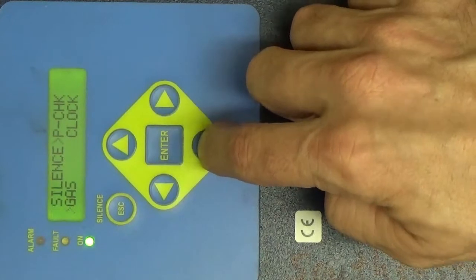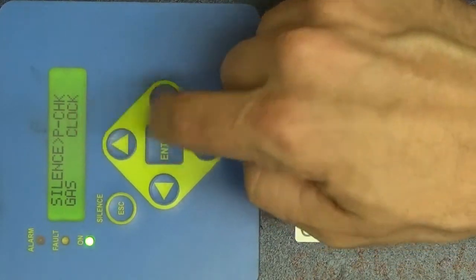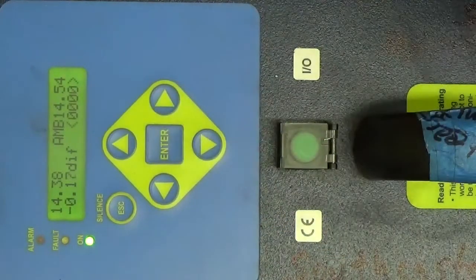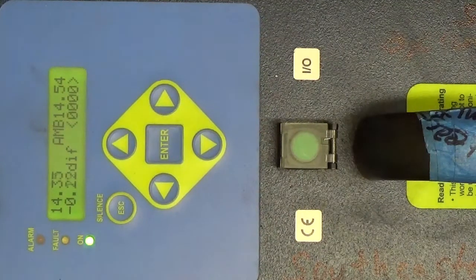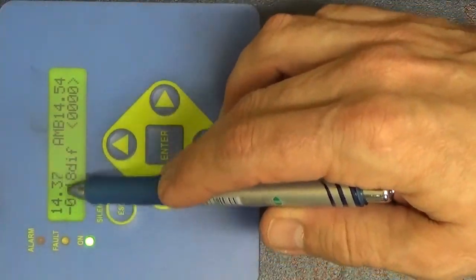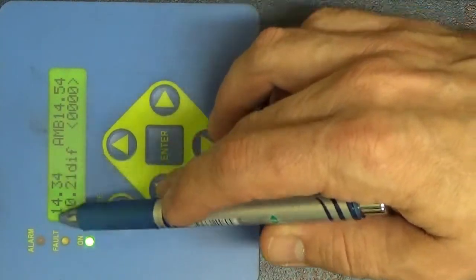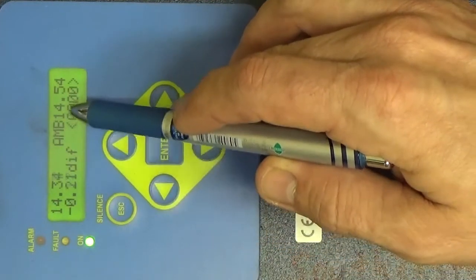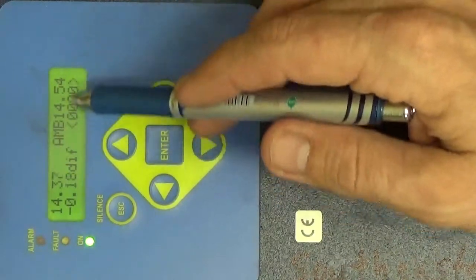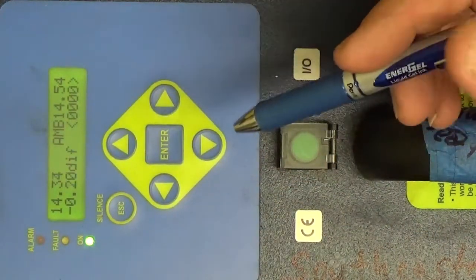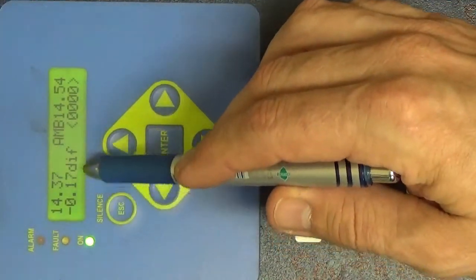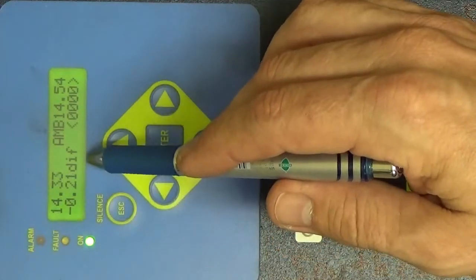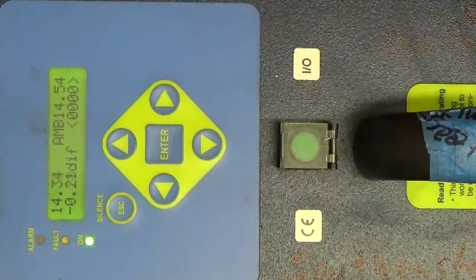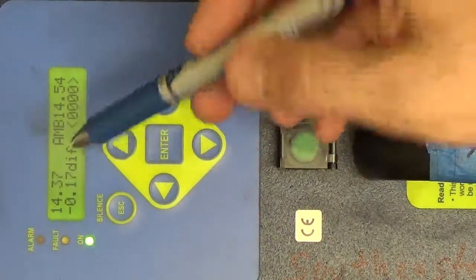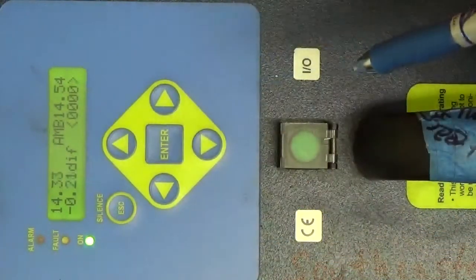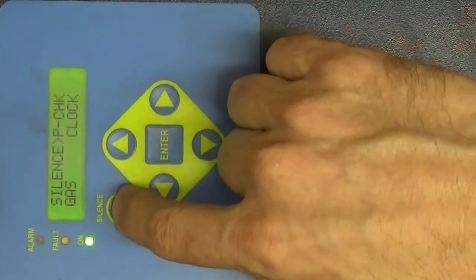And last thing I want to check, two more things to check here. One is called P-check, which is our pressure check. Go in here, and this is going to test the health of the pump. And so I want to check two numbers in here. One, what it's recording as the ambient pressure in the room. This is 14.54. As long as it's around 14 point something, you're fine. That's the ambient pressure. And then the other thing we're interested in seeing is what the number is in this lower left-hand side. And this is the actual pressure differential between what the pump is pulling to the outside air. That's essentially our vacuum pressure. And so we want to make sure that this number is in acceptable range. And we hit escape to get out of that menu.